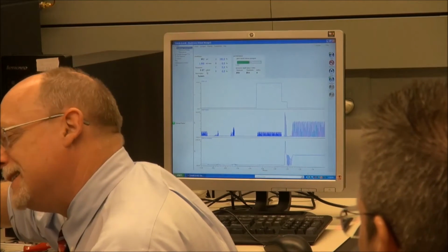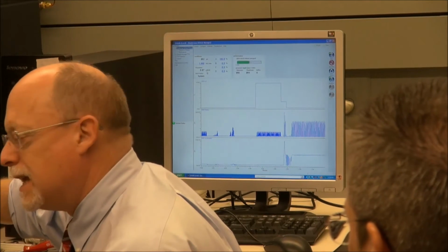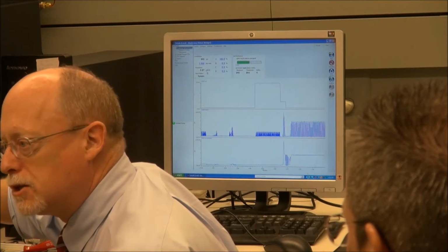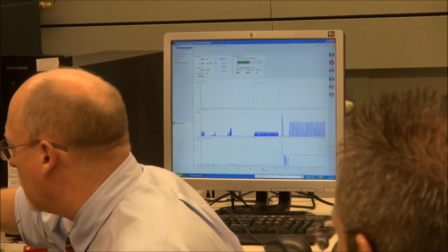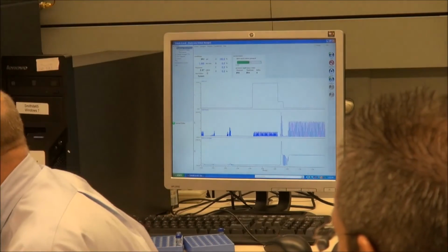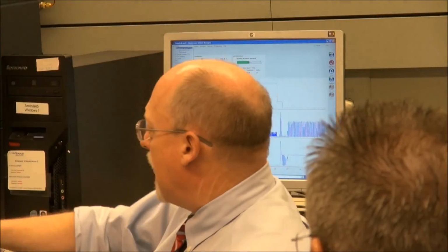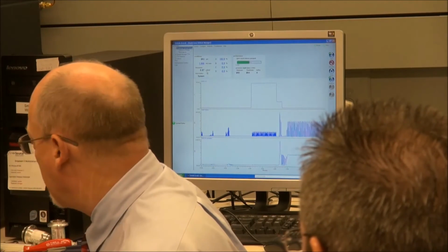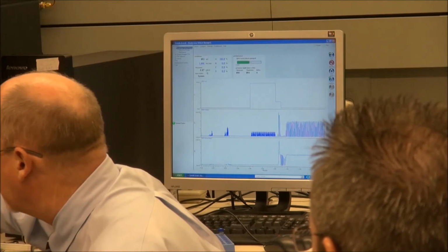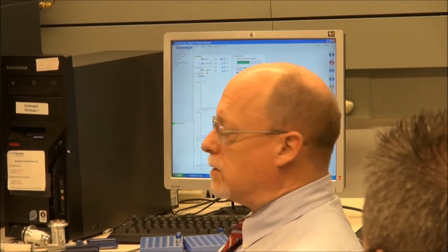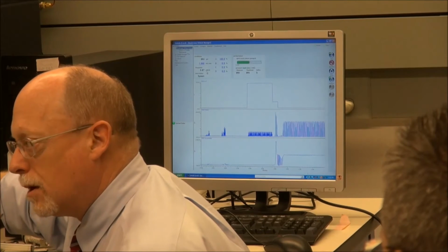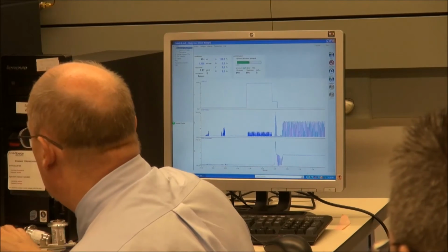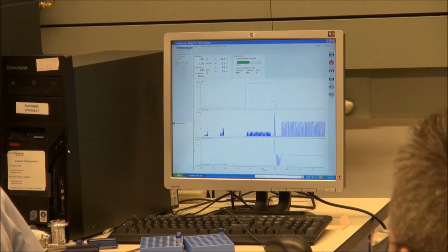Okay. Unfortunately, on an H class, this thing is so far over here that it's not really helping you much. But this is percussive right here, if I'm touching this. So, unfortunately, on an H class, since your seal wash pump is here, on a standard Acquity, your seal wash pump is here. And what will happen is, as this thing is percussing, it's like you taking a screwdriver and tapping your heads like that. So if you're trying to prime and you want to get the air out, especially in a standard Acquity, start your seal wash pump. Because it's like you doing like that, and every time you do that, you're helping to release air. It's not moving anywhere, it's just oscillating back and forth.